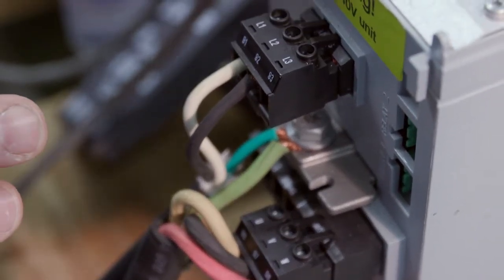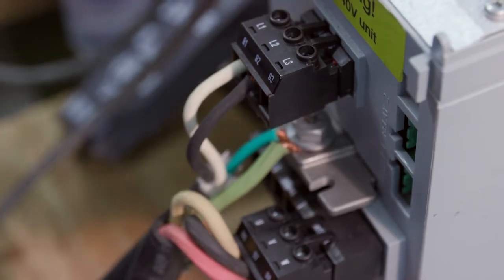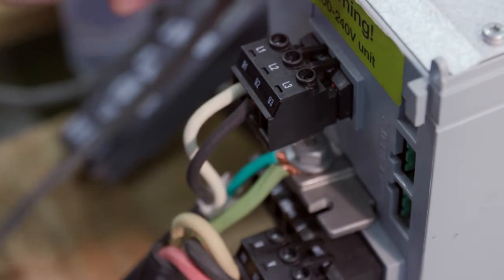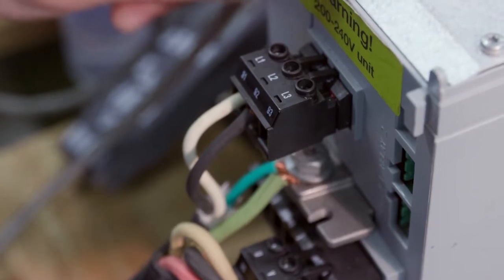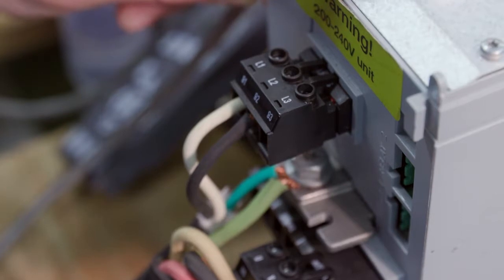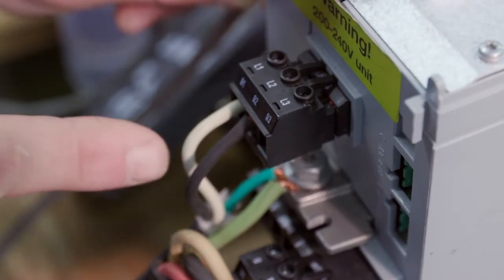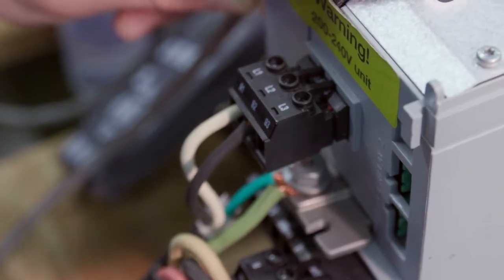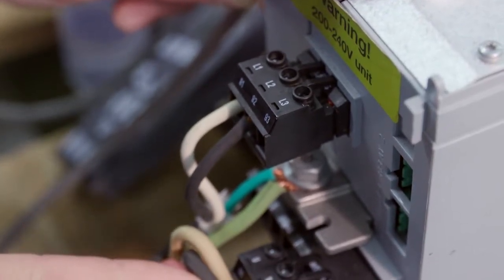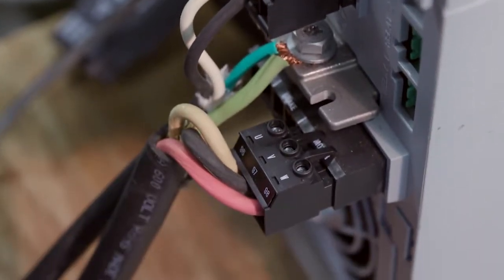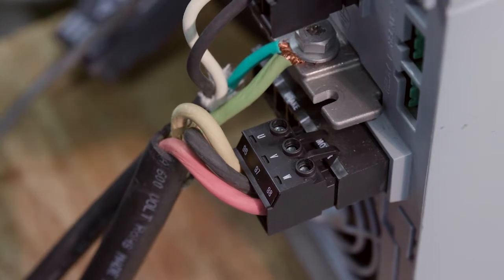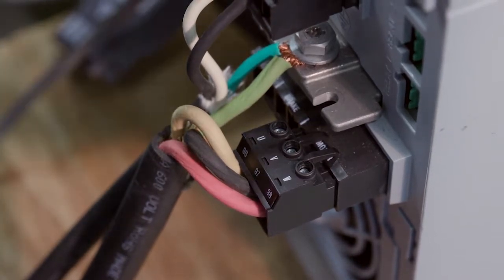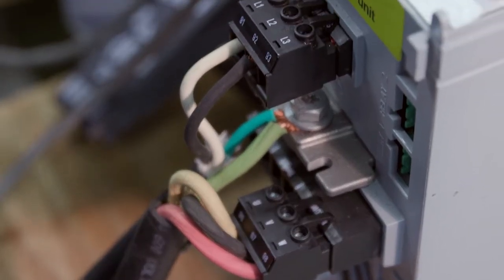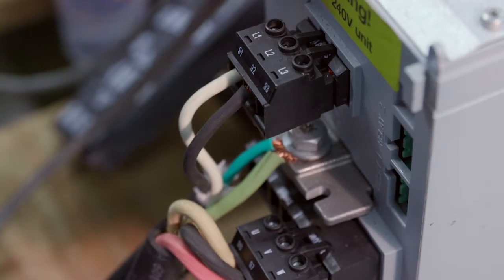And so we have L1, L2, and L3. What we've done here is we are bringing single phase in to the drive. The recommendation in the field, if you have single phase, is to order the dedicated single phase drive. In this case, we are just working with a 3-phase drive, however, bringing single phase in. So that's why our input wiring looks like it does. On the output is UVW going to the motor, and just like before, all these terminals are removable and replaceable, and underneath the L1, 2, and 3 in this small A-frame size is your ground lug.